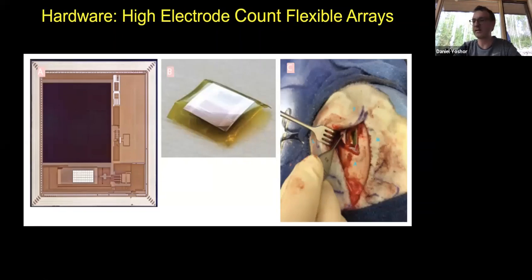And the chip is rendered flexible through extreme thinning, which allows it to conform to the curved surface of the brain. Because the electrodes sit on the cortical surface rather than penetrating into it, surgical implantation is simple. I've already implanted a prototype of one of these with Andreas Tolias at Baylor in a monkey. It's not functional, but it was just to test the materials compatibility and flexibility. We've implanted and explanted in a single monkey, not having stimulated or recorded with the device, but the basic biocompatibility over several months is quite acceptable, and the ability to conform to the brain seems promising as well.